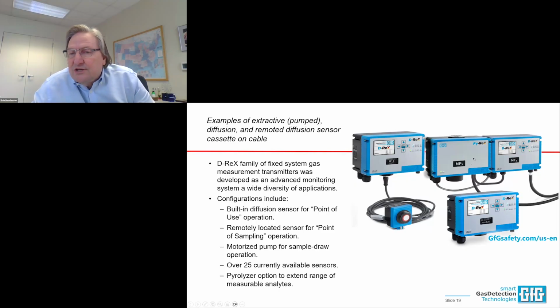There's no electrochemical sensor available to measure NF3, but we're still able to measure it. We take it through the pyrolyzer where the molecules are cracked apart and turned into HF molecules, which we are very good at measuring. So we measure the NF3 by breaking it apart into a different molecule, which we can measure. And since we get 3 molecules of HF for every 1 molecule of NF3 that goes into the system, it is really very sensitive and highly accurate for the gas that we actually need to measure. So that's an example of 3 different ways that we can configure the transmitter.